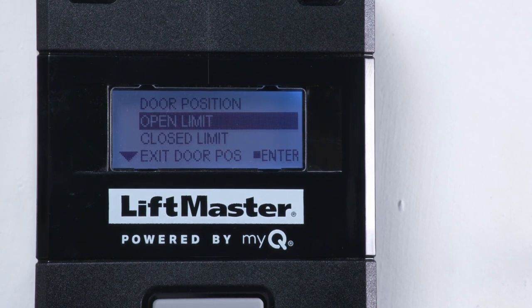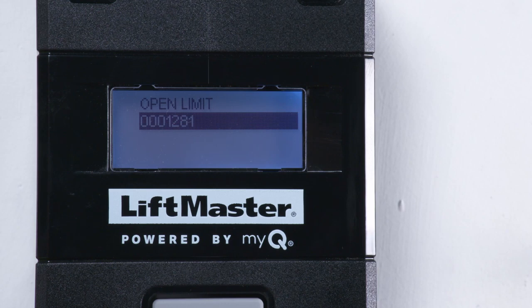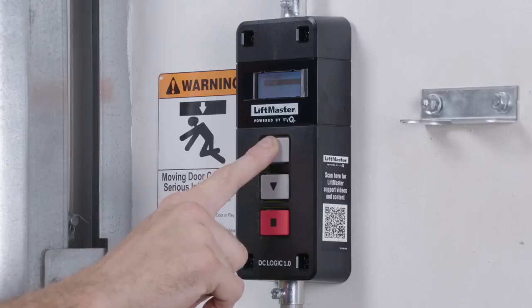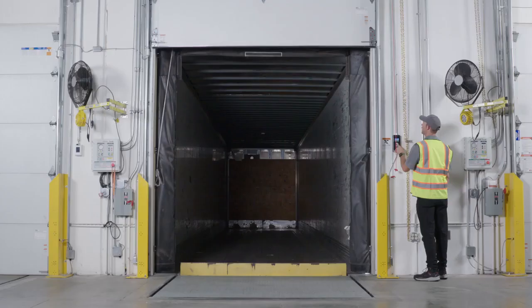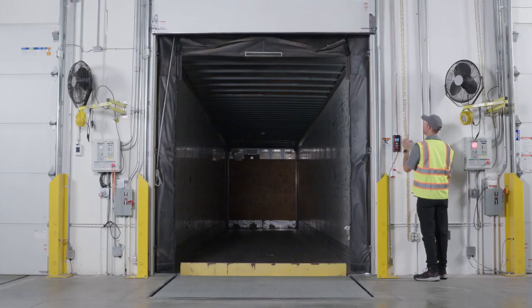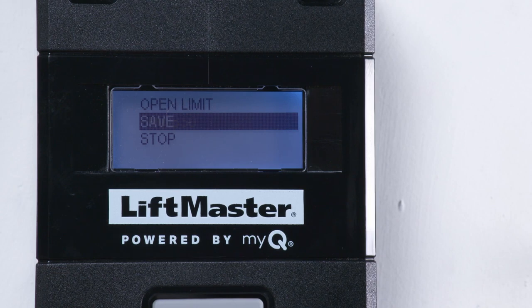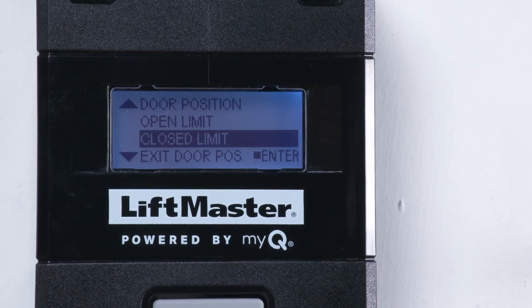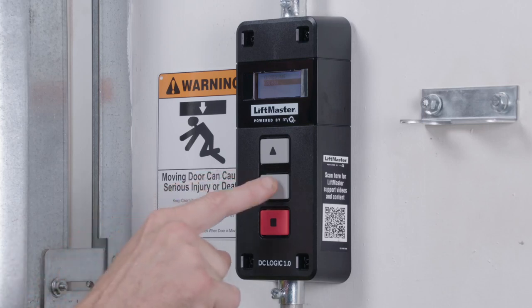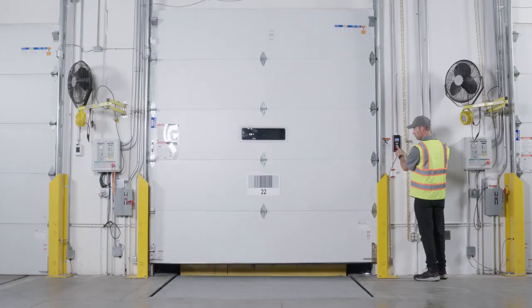Select Open Limit. Press Enter to show the encoder position. The display will show a number corresponding to the door position. Use the up arrow and down arrow to move the door to the fully open position. Press Enter to save. Select Closed Limit. Press Enter. Use the up arrow and down arrow to move the door to the fully closed position.